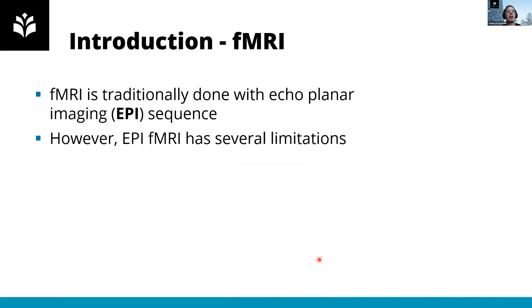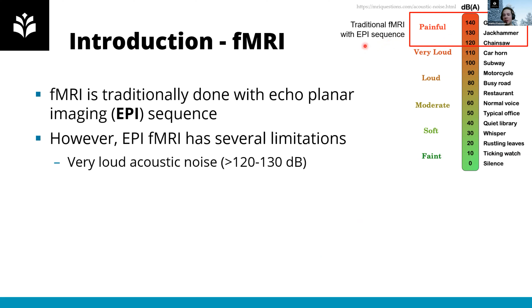First is the very loud acoustic noise, which can be over 130 decibels. If we look at this chart here, it's comparable to a jackhammer or even a gunshot. So it's a really noisy approach. In addition, as with MRI generally, it's very sensitive to movement and image artifacts, and the EPI sequence is particularly sensitive to these. Here's one result of a clinical study where they found that almost 60% of all clinical data is affected by motion artifacts.